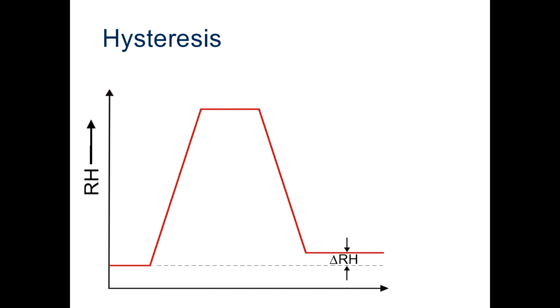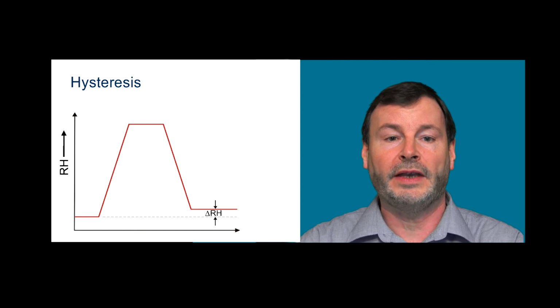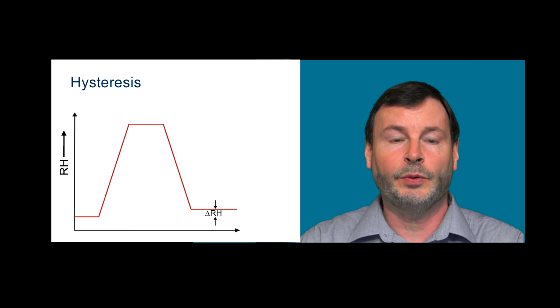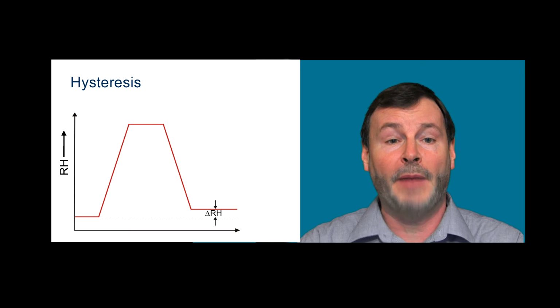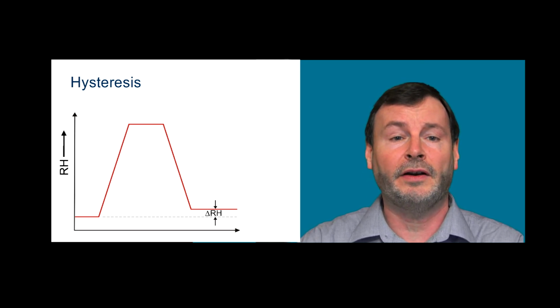In this particular example, we see an RH measurement device was at a relatively low or dry relative humidity value. It was then exposed to a much higher humidity level for an extended period of time, and then brought back down to that lower, drier environment. Hysteresis occurs when the humidity measurement device does not return completely to that low value. That difference, delta RH, shown on this graph, is the hysteresis value, the non-return value when brought back to the initial low humidity point. Now, this offset can, in some sensors, be quite small, but in other sensors, depending on the magnitude of the humidity and the length of the exposure, it can be several % RH. It can be quite significant.